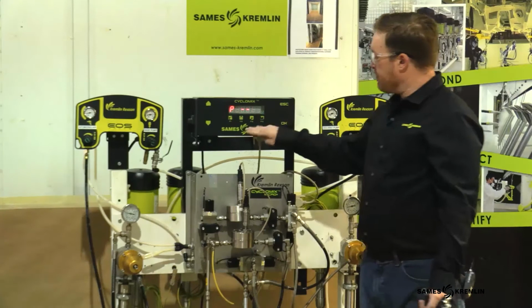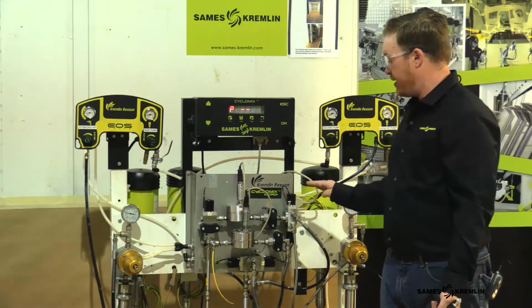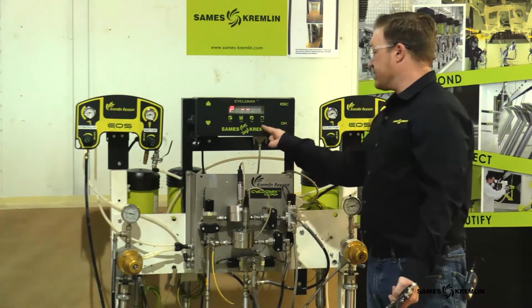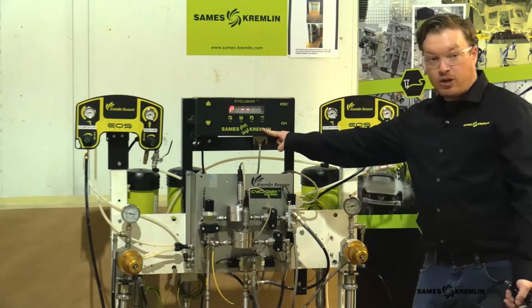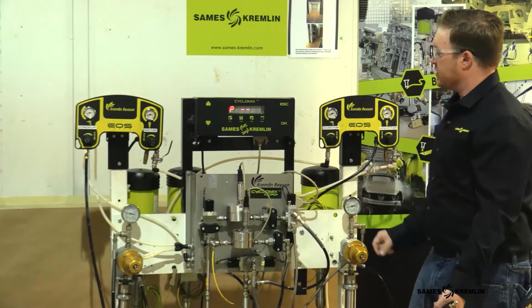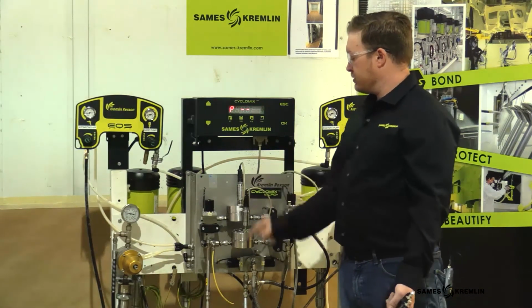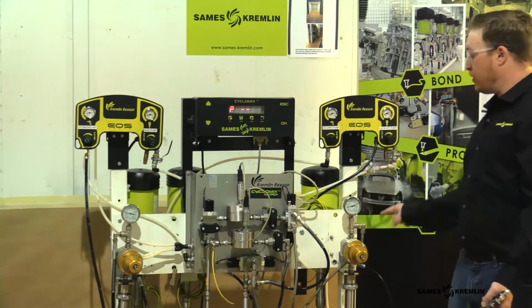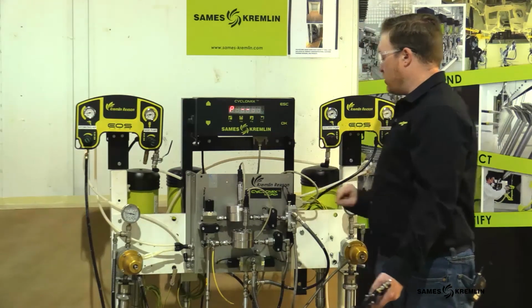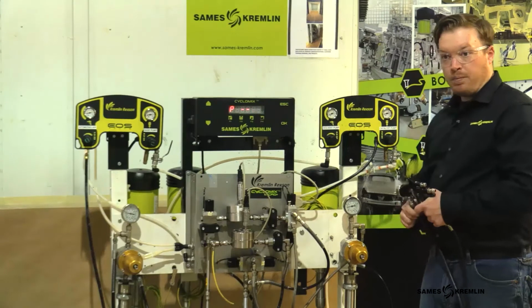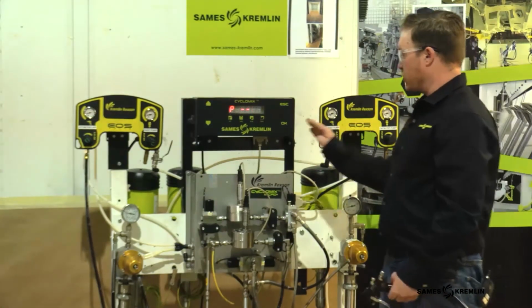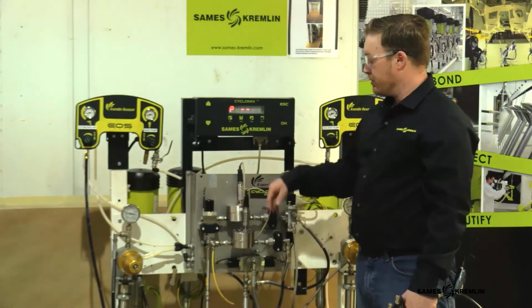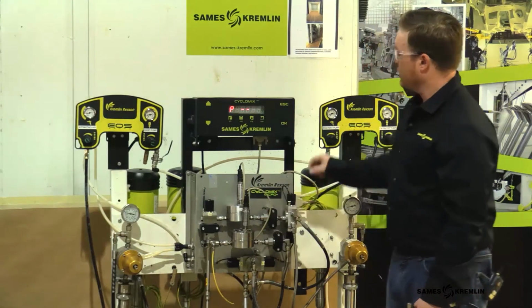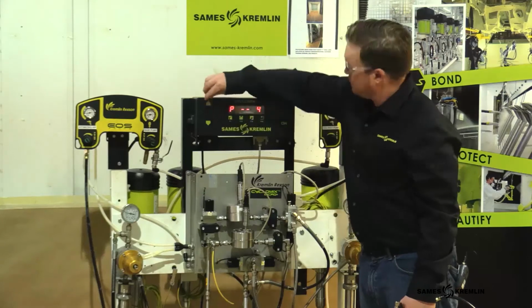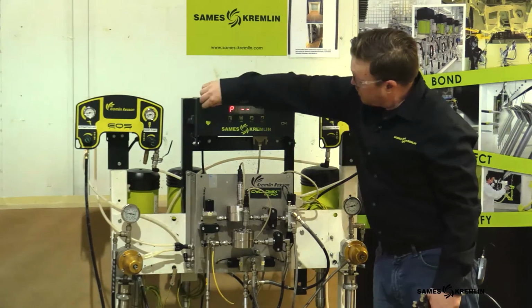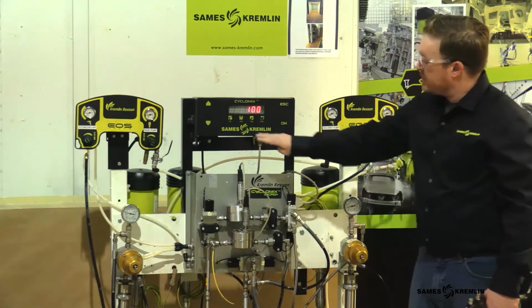So this P11, I'm not going to hit the OK button here because it's going to start to simulate a mixing event. But this is our parameter for the ratio test. And it's nice because what it does is it's monitoring just the pulses and the air and the injection. It's not concerned about obviously ratio accuracy or any other parameters that could potentially fault out the machine. This is strictly looking for the proper values and flow rates from our flow meters. So we'll go up to P12 now, and P12 will be set at 100 from the factory.